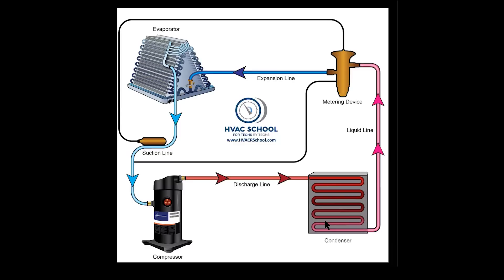The first analogy: a tank of R410A has maybe 25 pounds of refrigerant in it, which could charge two to three residential air conditioning systems. And yet the pressure inside that tank is not high — it's static pressure based on the saturation chart, because there's liquid and vapor present. The reason it's not high is because it has achieved stability with the outdoor air temperature. So something having a lot of refrigerant in it by its very nature doesn't cause high head pressure.